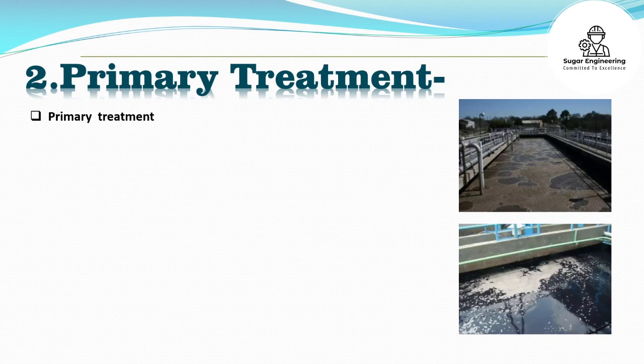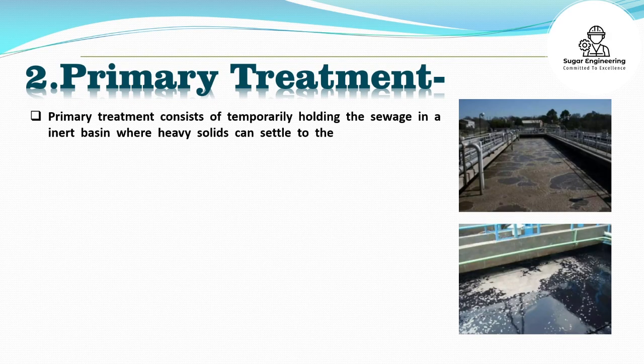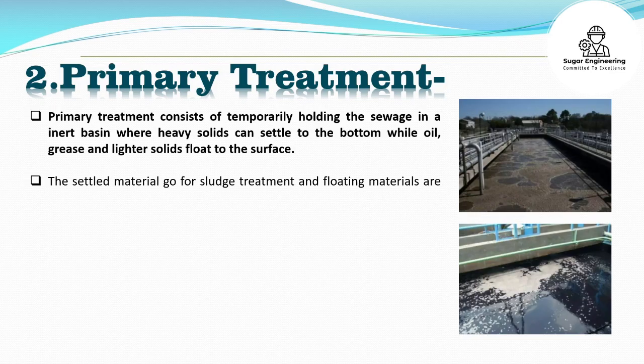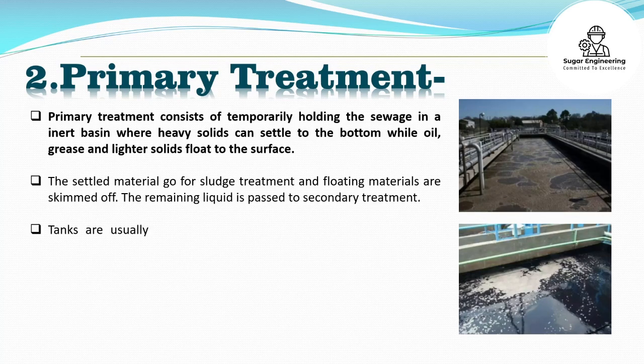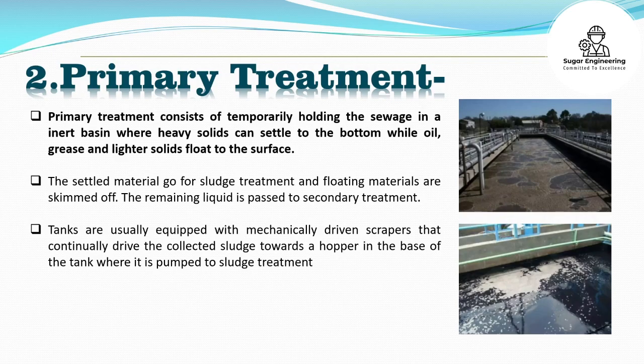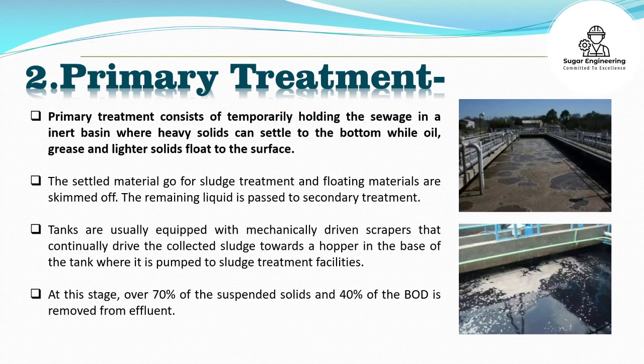Primary treatment consists of temporarily holding the sewage in an inert basin where heavy solids can settle to the bottom while oil, grease, and lighter solids float to the surface. The settled material goes for sludge treatment and floating materials are skimmed off. The remaining liquid is passed to secondary treatment. Tanks are usually equipped with mechanically driven scrapers that continually drive the collected sludge towards a hopper in the base of the tank where it is pumped to sludge treatment facilities. At this stage, over 70% of the suspended solids and 40% of the BOD is removed from effluent.